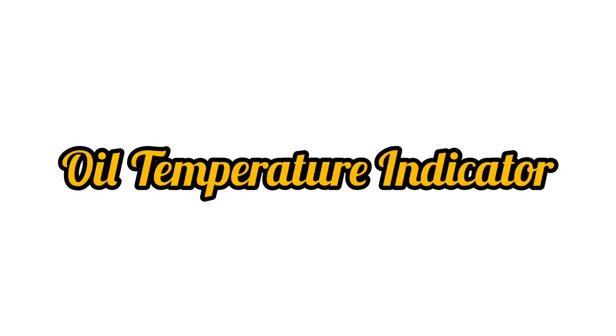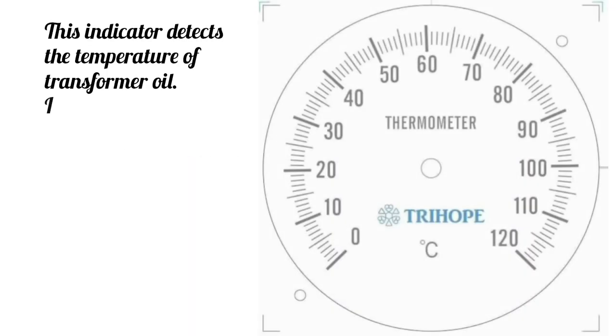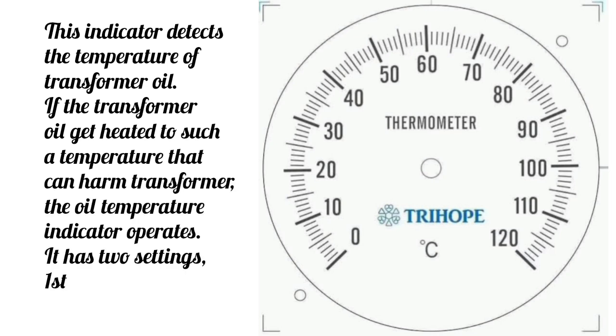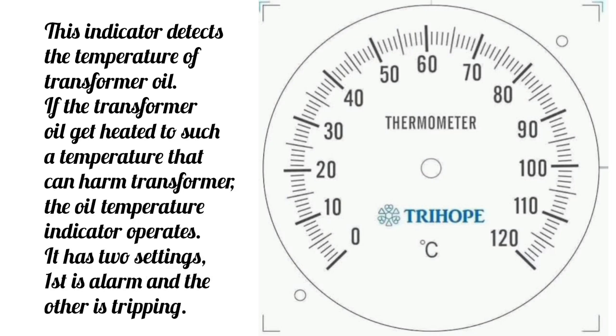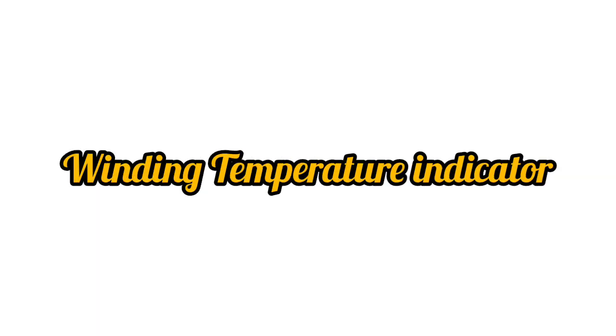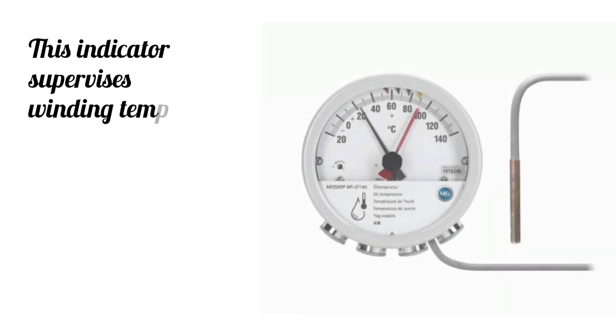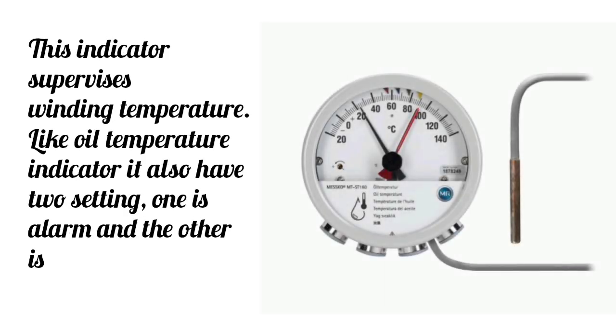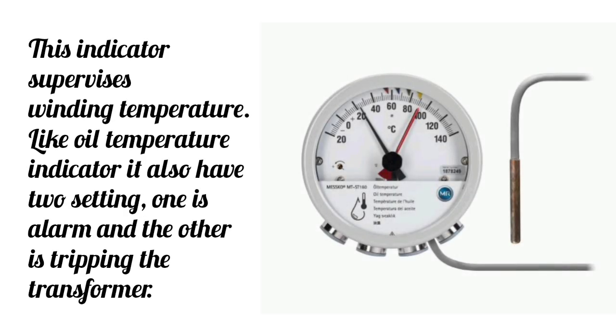Oil temperature indicator. This indicator detects the temperature of transformer oil. If the transformer oil gets heated to such a temperature that can harm the transformer, the oil temperature indicator operates. It has two settings. First is alarm and the other is tripping. Winding temperature indicator. This indicator supervises winding temperature like the oil temperature indicator. It also has two settings. One is alarm and the other is tripping the transformer.